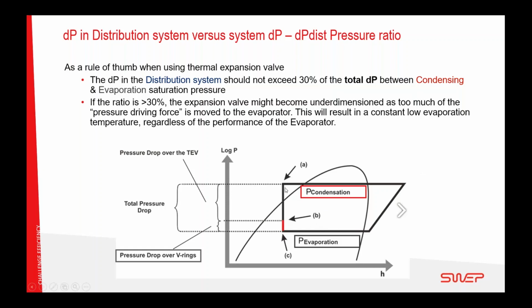This is the log p-h diagram. Again, I will not go into this too much, but up here is the condensing pressure. It's the same pressure all the time here. And down here is the evaporating pressure. So the same pressure along this horizontal line. Between the condensing pressure and the evaporating pressure, there is an expansion valve. So all this is what the expansion valve does. It goes from the high pressure to the low pressure.